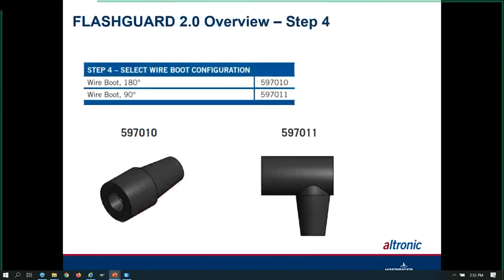And then step 4, what type of boot you're going to put on to meet up with the Teflon extension here. You've got either the 597-011, which is a 90 degree, or you've got the 597-010, which is a straight. And it's pretty much just up to customer preference. Just run the secondary wire through, and then it pops onto the top of the Teflon extension. And once it's on, they don't come off. Pretty tough to get off of there.